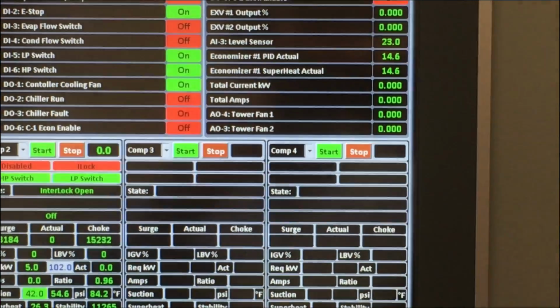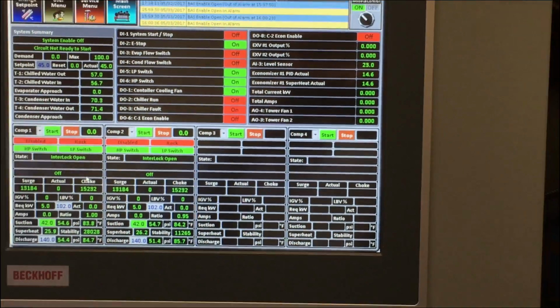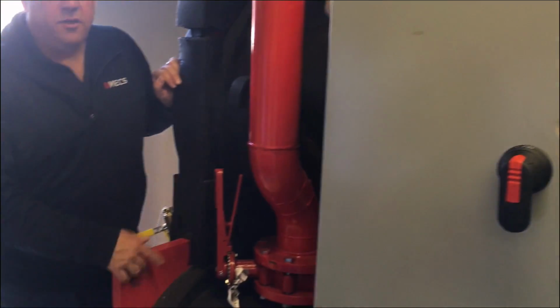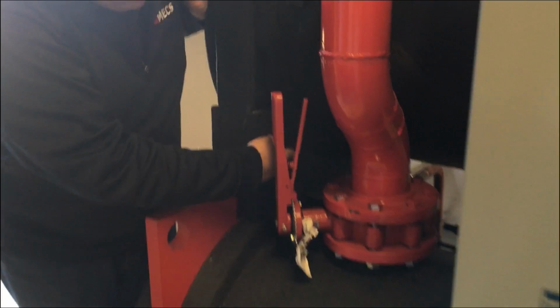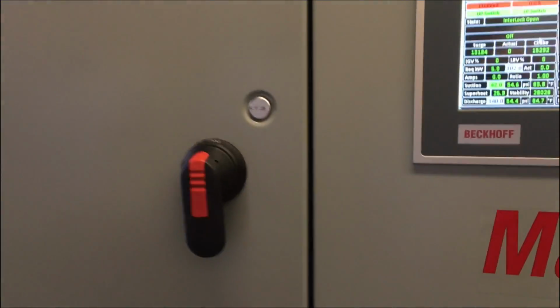The level sensor, if you can see, it's right through here. You can see it this way. It's on the other side of the machine, but it points this way. So we control this chiller by a level sensor, and the level sensor is in the condenser. So we try to maintain a certain level in the condenser, which in turn should be a certain level in the evaporator. And as this goes up, it's going to open the expansion valves to draw it back down.